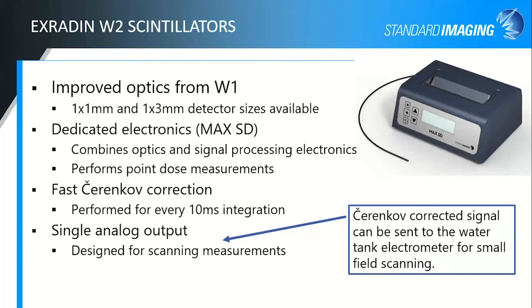If you wish to use your W2 in the water tank, the MaxSD can convert that Cherenkov corrected measurement into a single analog output value. It is also scaled up just slightly so that it's more in the range of the expected signal with your water tank electrometer. So you're not trying to measure these extremely small signals with the water tank or with the triax cable, a longer triax cable potentially for the connection between the MaxSD and the water tank. Actually, it's not longer. We send you a cable for that.